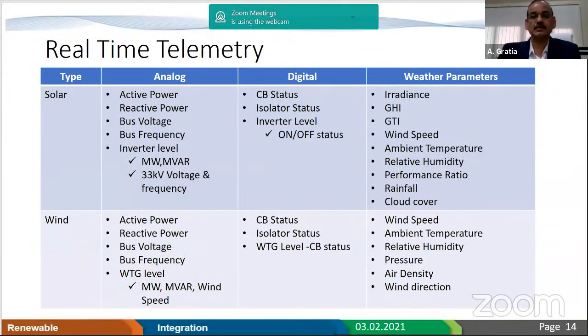The difference between normal SCADA and REMC: normal SCADA operates up to 110 kV level only. When the Unified Load Dispatch Scheme was commissioned in 2000 by a World Bank project, the philosophy was to measure and monitor the grid at 110 kV and above, mainly for security monitoring of the system. Whereas REMC's injection level is only 33 kV, 11 kV, and maximum 66 kV. Those monitoring needs a special measurement and metering system, so REMC's metering system is slightly special. Measurement is done at the 33 and 11 kV level, with analog and digital parameters. There isn't much difference from normal SCADA otherwise, except the voltage level is low.